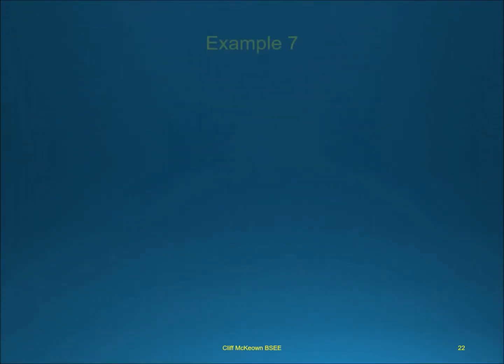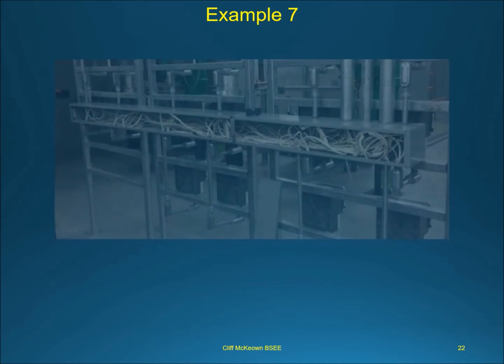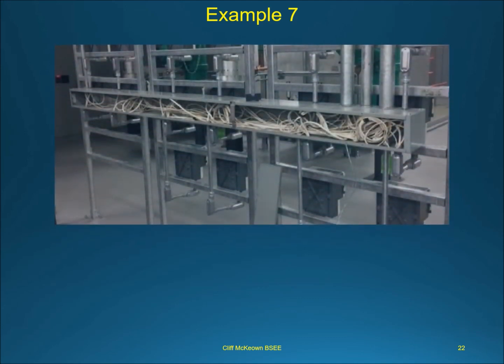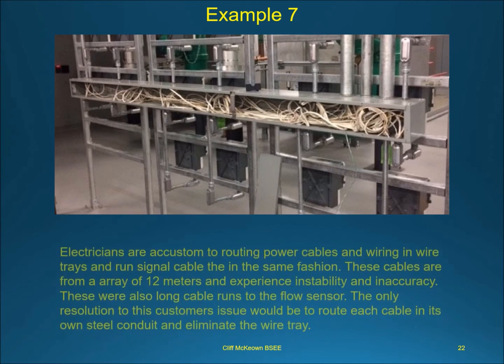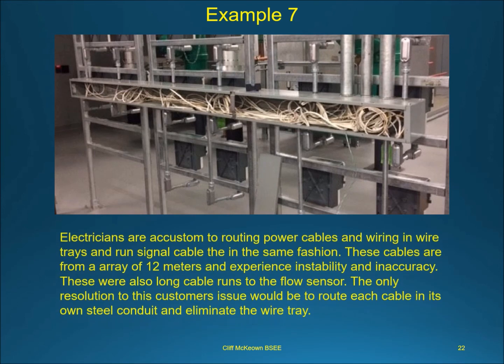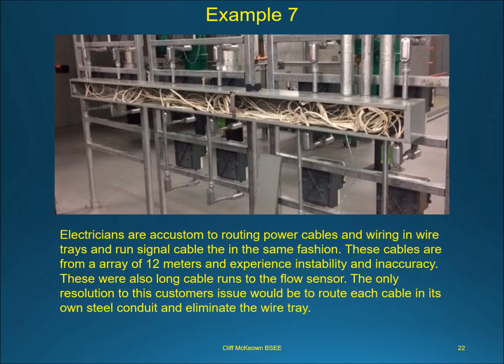Electricians are accustomed to routing power cables and wiring in wire trays, and ran signal cable in the same fashion. These cables were from an array of 12 meters and experienced instability and inaccuracy, with long cable runs to the flow sensors. The only resolution to this customer's issue would be to route each cable in its own steel conduit and eliminate the wire tray.